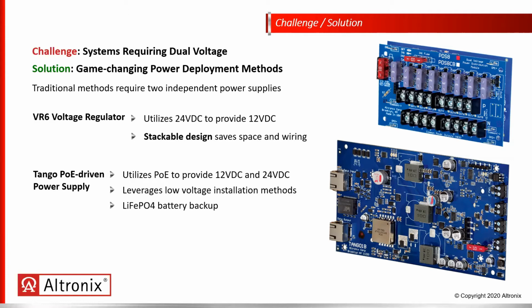The Tango product is designed to utilize 4P PoE to provide both 12 and 24 volts DC simultaneously. It's going to allow you to design and deploy a system leveraging low voltage installation methods, using Cat 5e or higher cabling, Cat 6 cabling, delivered in the same wire trays as our other low voltage cabling, eliminating the need for conduit as well as specific circuit breakers in an electrical panel to manage the system's power.